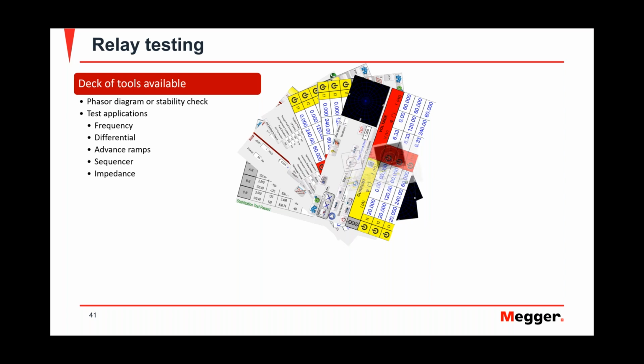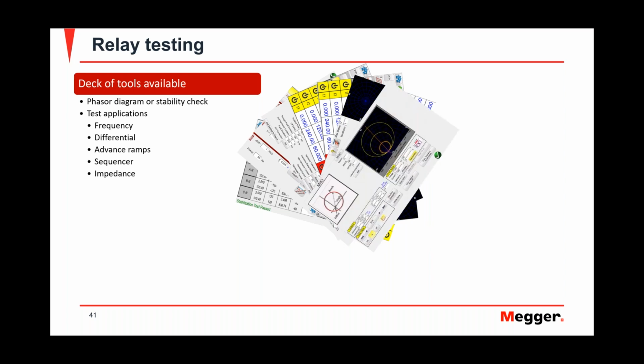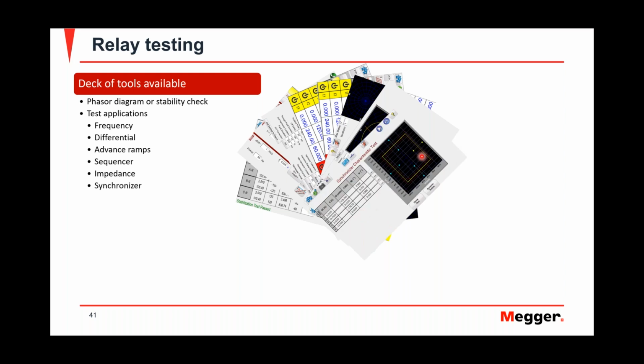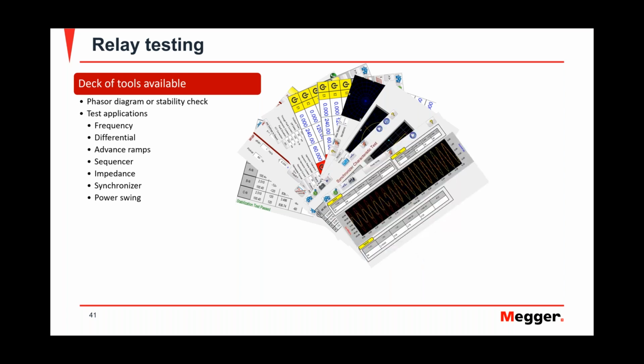So you have a sequence of events that happen, and you provide the relay with different voltages and currents depending on the sequence that you set up. There are some impedance tests, and there are multiple screens that you could use depending on what type of impedance testing you are doing. A synchronizer is good for generator controllers. It will allow you to see at what voltage and at what frequency it will change for you, and it will allow you to see when the relay closes in order to connect a generator to a system. You have a power swing tool that would allow you to simulate power swing conditions so that you could test, especially for generator protection. You could use this tool a lot.